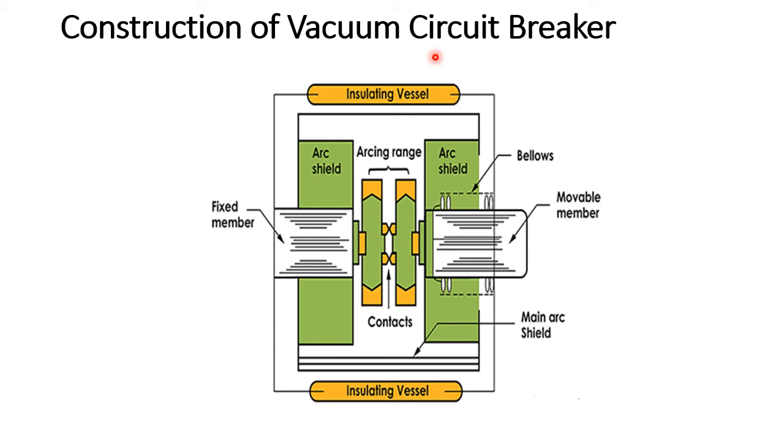The closing spring recharges automatically after the operation of the circuit. There will be a tripping push button that activates the spring immediately after detecting some high voltage and breaks the circuit. So the auxiliary switch contact and the primary contacts are separated. The auxiliary contact provides a signal to the external equipment to initiate the shutdown or alert the user.